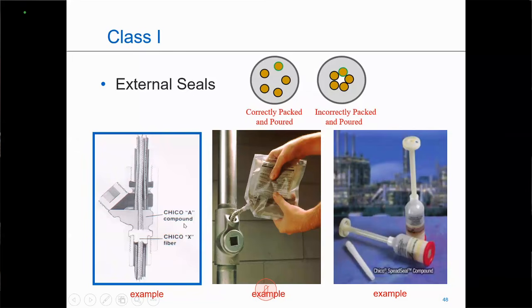Also, these units are all tested by UL as a complete assembly. So if you were to have a compound that was being used with a different manufacturer's sealing fitting, for example, if sealing fitting A wanted to use the manufacturer B compound, you would actually have to see if that sealing fitting has been tested to go with that particular compound. The code tells us that the sealing fitting shall be listed for one or more compounds. So if it's not listed for use with that particular compound, then that compound could not be used in that fitting. My recommendation is if you use manufacturer A for the sealing fitting, use manufacturer A for the compound. If you use manufacturer B for the sealing fitting, use manufacturer B for the compound and fiber.